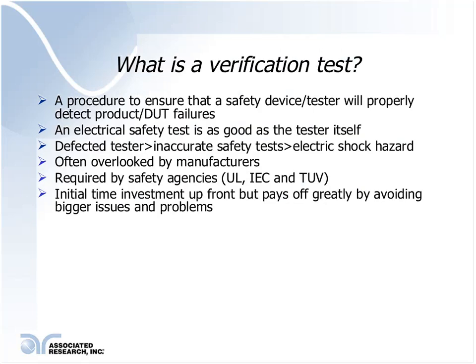Okay, having said that, let's jump directly into what we're going to be learning today in this webinar. So what is a verification test? Well, as the word implies, it is a procedure to ensure that a safety device or tester will properly detect product or device under test failures.